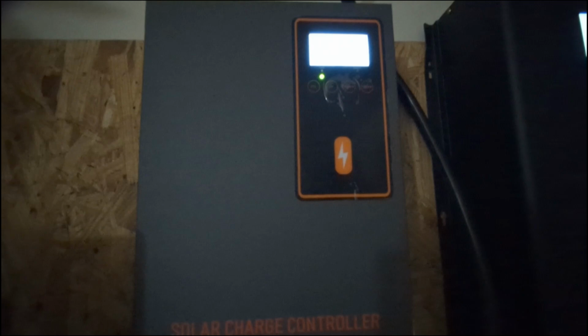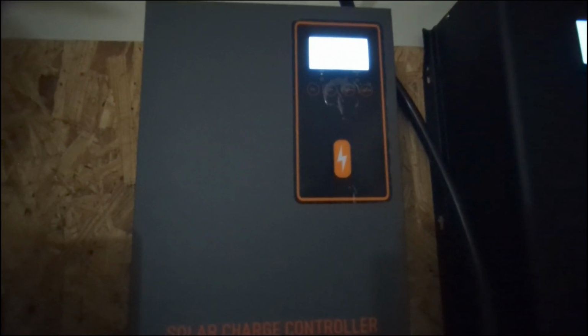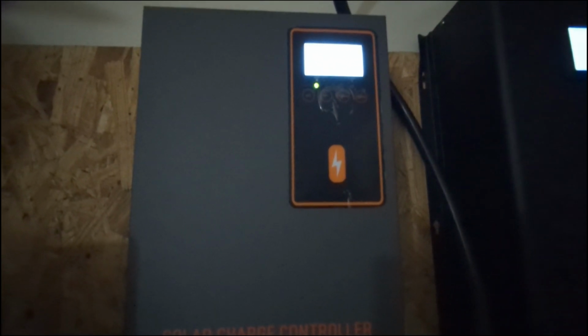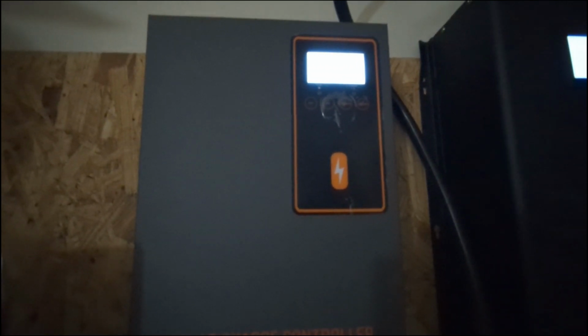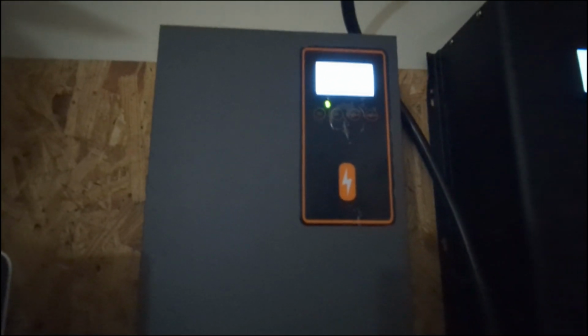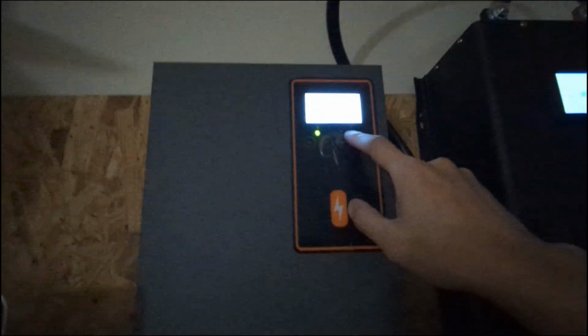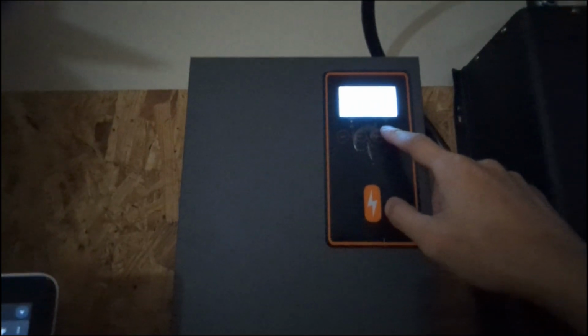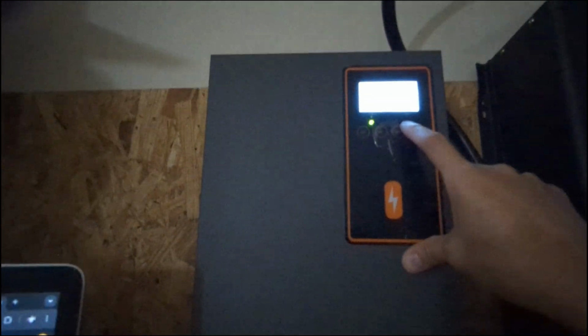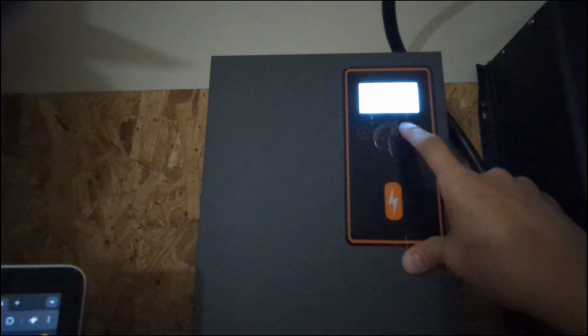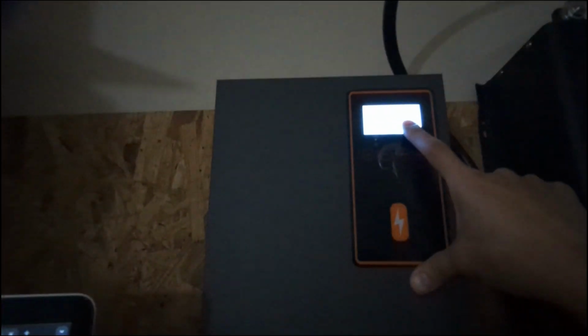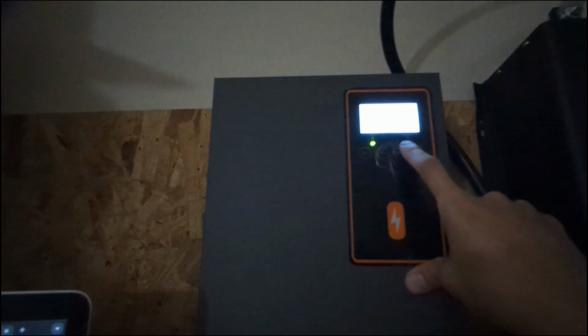I do want to mention that if you have your equalization or floating voltage set up and your unit is getting to that point where it tries to top off the battery, it does flash an error message telling you that it has hit it. That's a kind of little quirk of it - it's not an error per se, but when it hits it, it kind of shows you an error with an error code, and if you go back to the menu, it tells you what happened there.